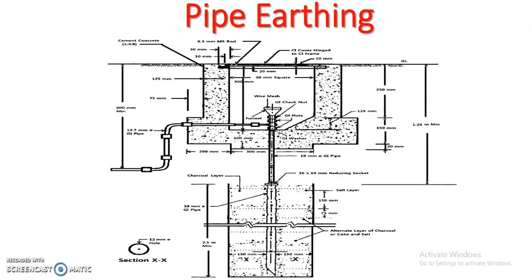So in case of a pole mounted substation, we can use pipe earthing. So this is our layout of pipe earthing. In this case, a number of layers of charcoal and salt are to be filled in an alternate manner. So these are the layers of salt and charcoal, and one GI pipe having a diameter of 38 mm is inserted in that hole. Again it is supported with a GI pipe of 19 mm diameter, and one funnel is provided at the top where you can input the water.